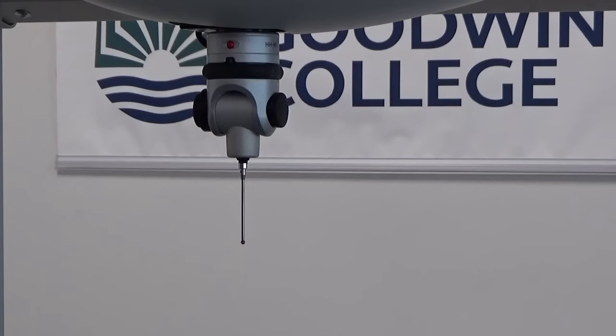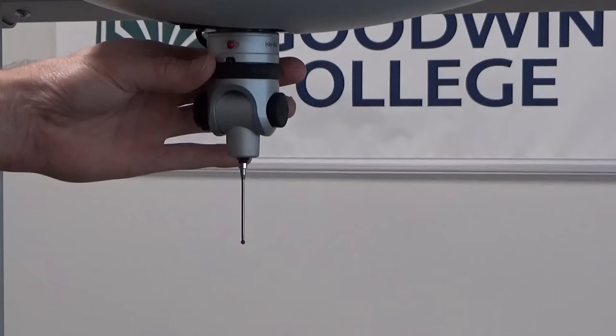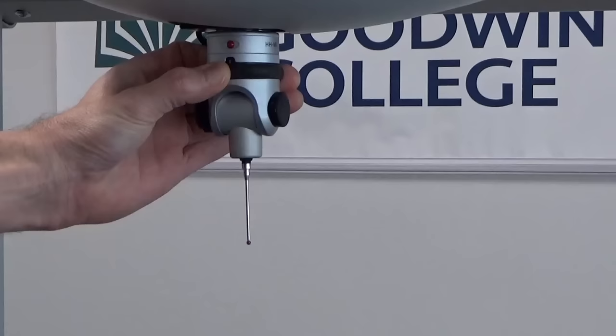We have a new probe tip on. It is a 50 millimeter long probe with a four millimeter ball at the tip. This is on a manual wrist which means that you change this manually and the angle manually for wherever you want to probe.